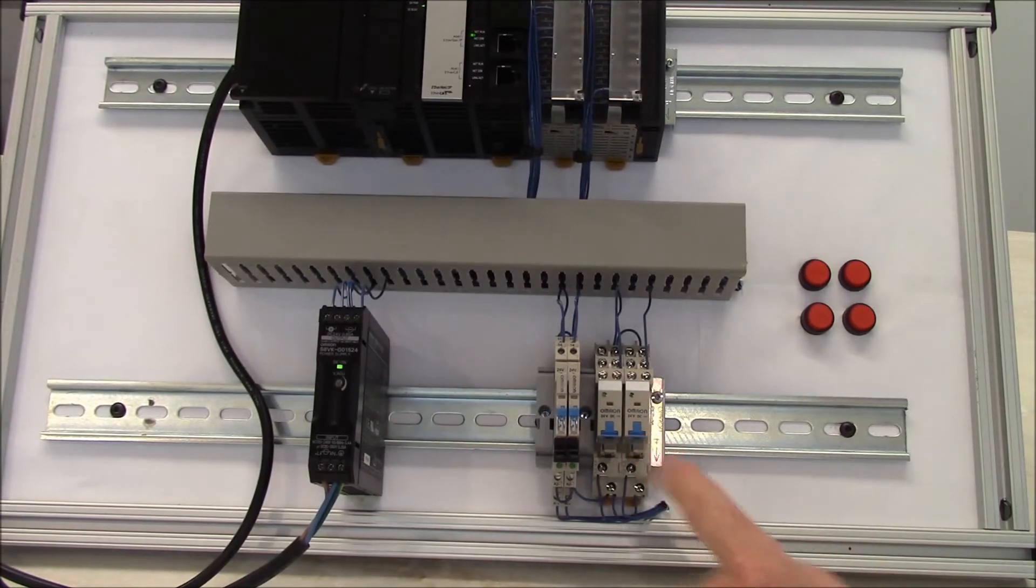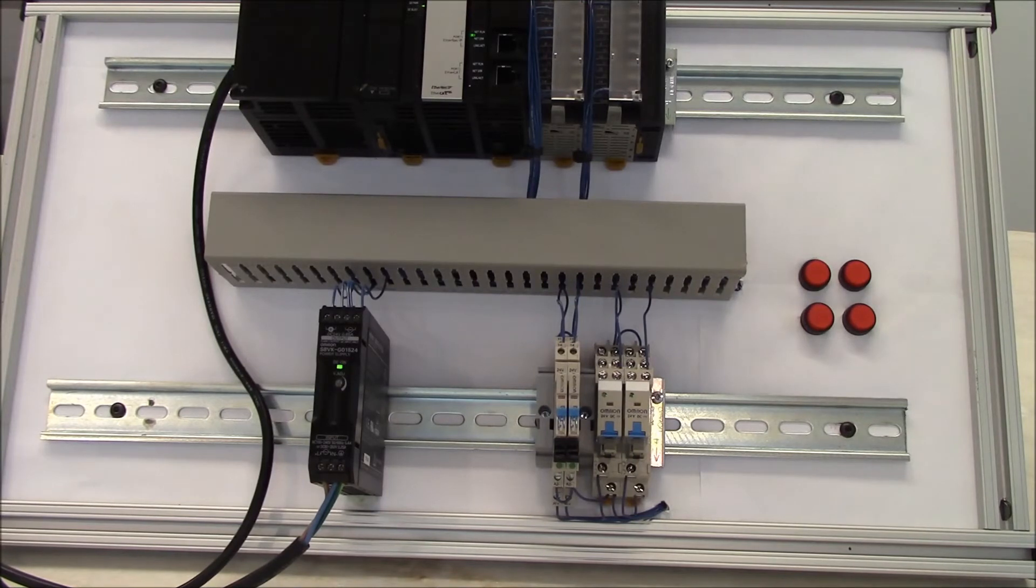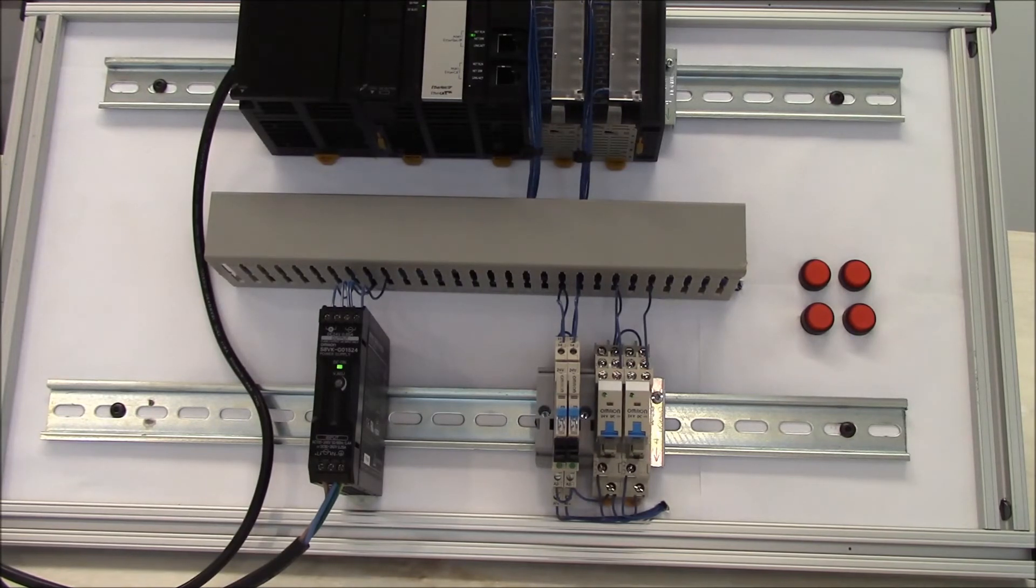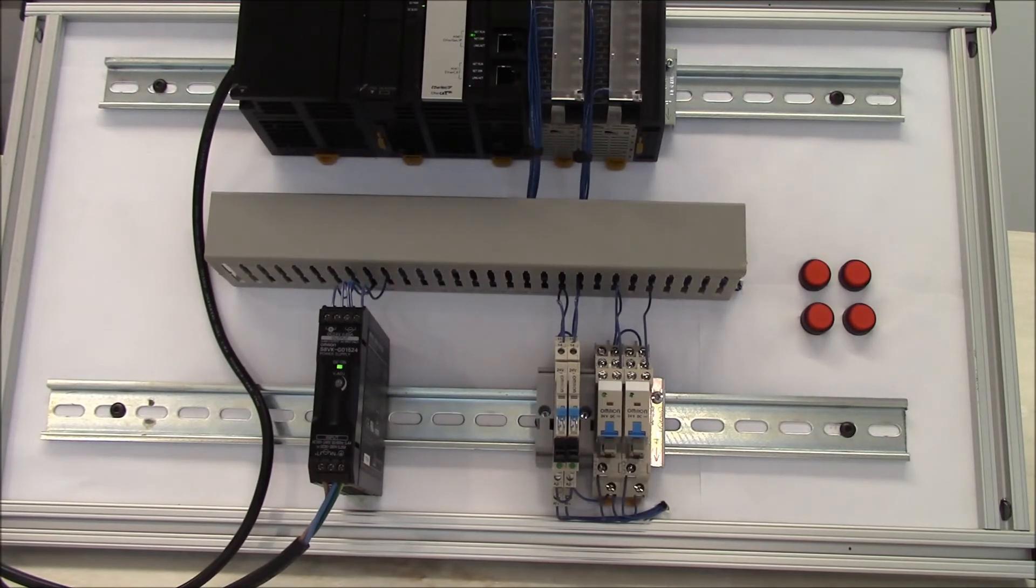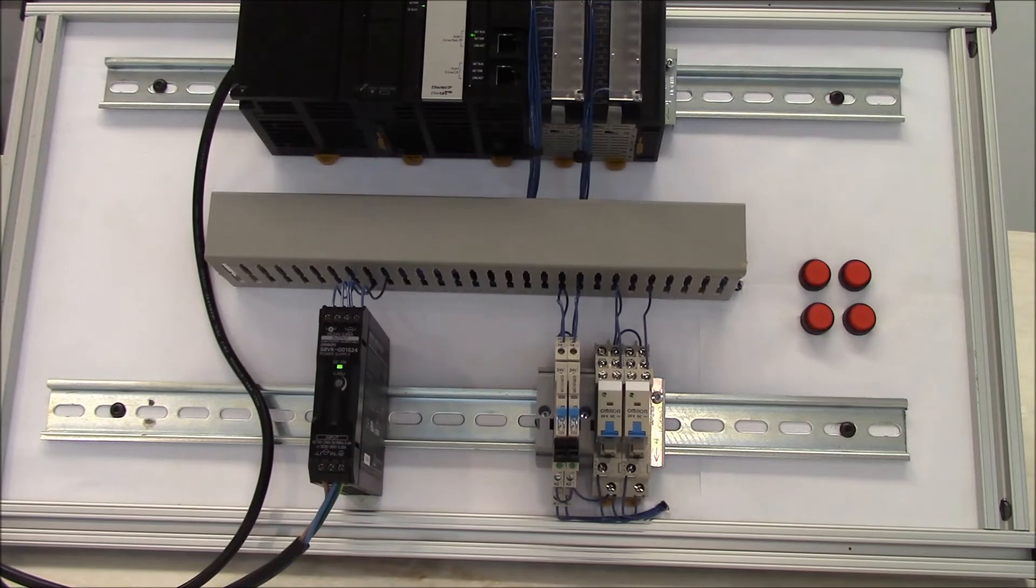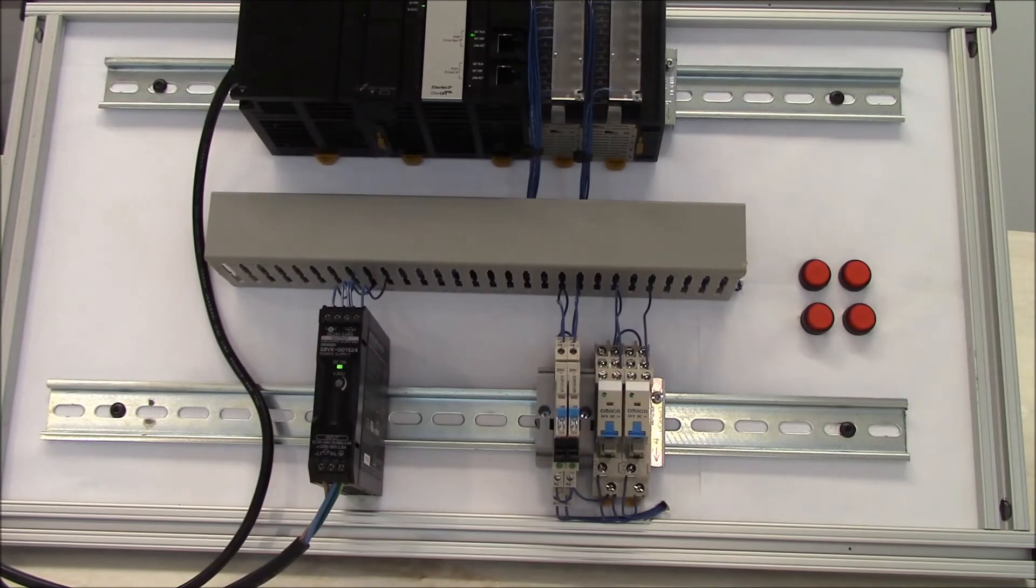On the G2RS, we offer a single-pole double-throw. It has a 10-amp contact rating, and you can get anywhere between 100,000 to 700,000 electrical operations depending on the current you're running. We also do offer it in a double-pole double-throw contact arrangement, and there you can get 5 amps at 100 to 1,000,000 electrical operations depending on the current you're running.